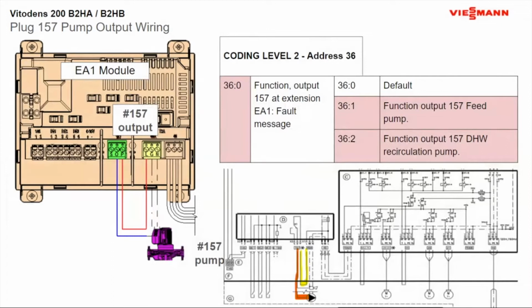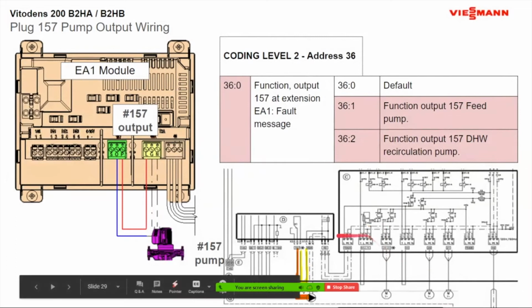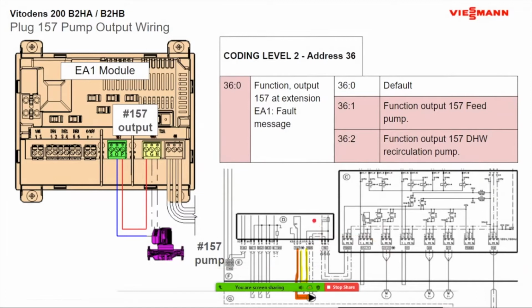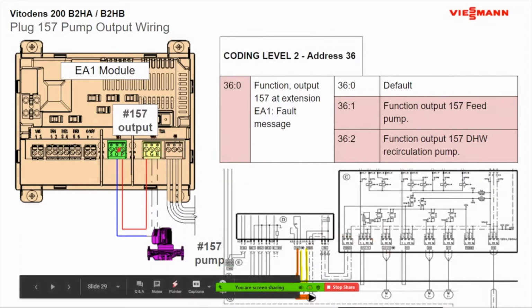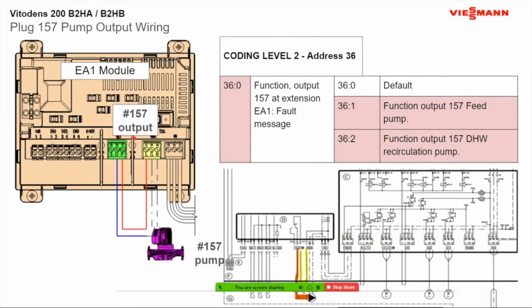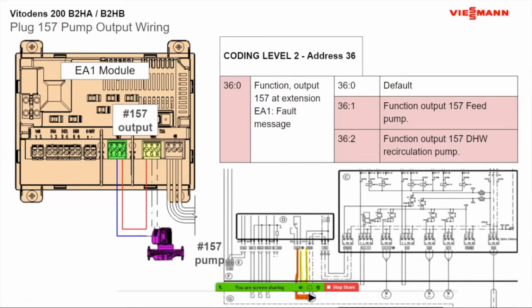So at the bottom here, I gave you a little quick wiring diagram with a marker, just so you can get an idea of that 157 pump output that they asked you to pick through your startup wizard. So now you can see you're going to go from L over to P to power this relay. And once the contact is called in by your pump output, or your thermostat or your relay, it now powers up O over to the pump, and now your pump will be energized. But you can also change this to do different functions as well.